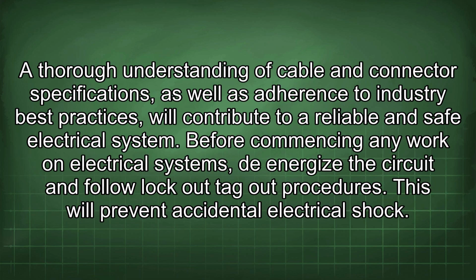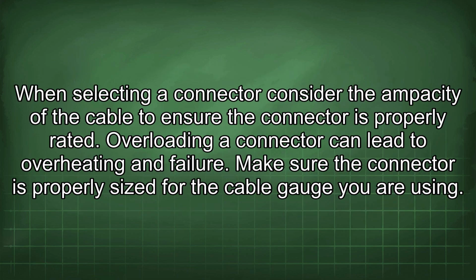A thorough understanding of cable and connector specifications, as well as adherence to industry best practices, will contribute to a reliable and safe electrical system. Before commencing any work on electrical systems, de-energize the circuit and follow lockout-tagout procedures. This will prevent accidental electrical shock. When selecting a connector, consider the ampacity of the cable to ensure the connector is properly rated. Overloading a connector can lead to overheating and failure. Make sure the connector is properly sized for the cable gauge you are using.